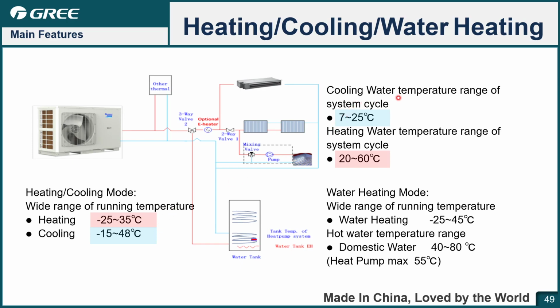And for the cooling circulation, the temperature range is from 7 to 25 degrees Celsius. For heating circulation, it is 20 to 60 degrees Celsius. And for hot water, the operation range is minus 25 to 45 degrees Celsius. The hot water you can get is from 40 to 80 degrees Celsius. However, the maximum temperature by the heat pump is 55 degrees Celsius, so above 55 up to 80 degrees Celsius is achieved by the e-heater inside. For the VERSATI 3, I think this range is very wide for operation and customer usage.